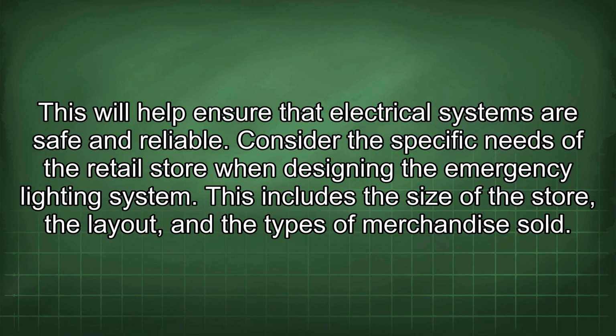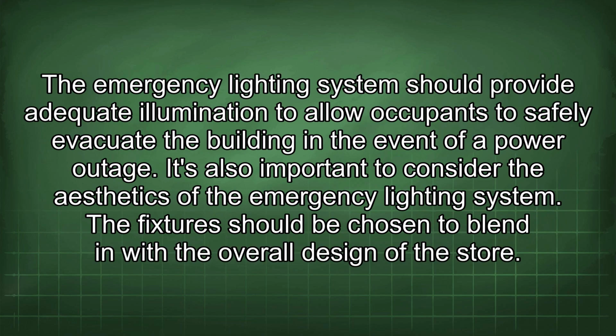Consider the specific needs of the retail store when designing the emergency lighting system. This includes the size of the store, the layout, and the types of merchandise sold. The emergency lighting system should provide adequate illumination to allow occupants to safely evacuate the building in the event of a power outage. It's also important to consider the aesthetics of the emergency lighting system. The fixtures should be chosen to blend in with the overall design of the store.